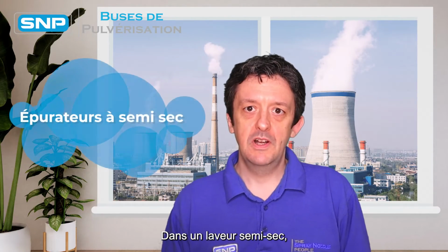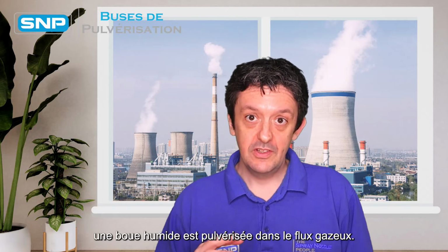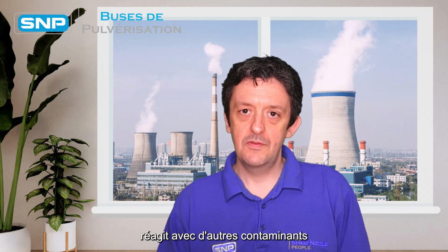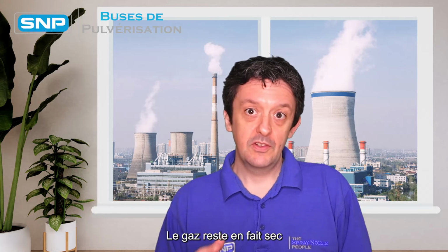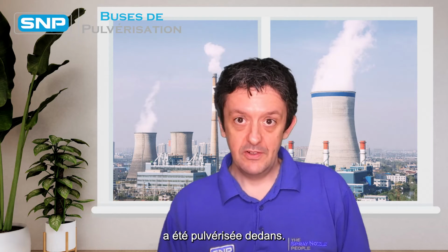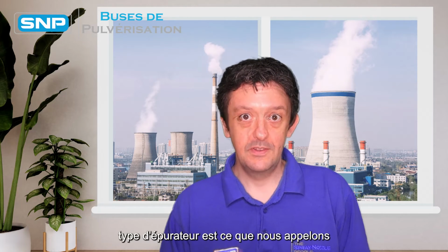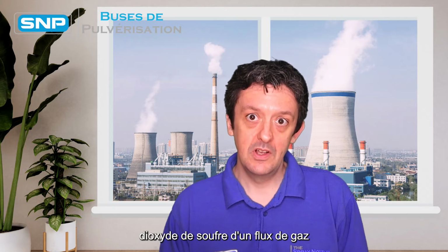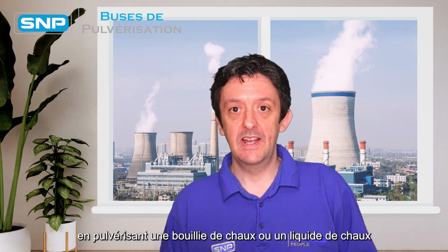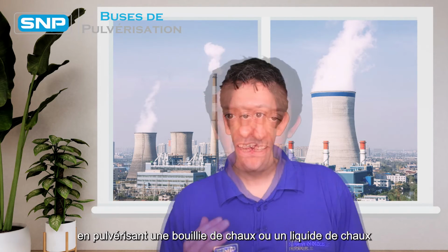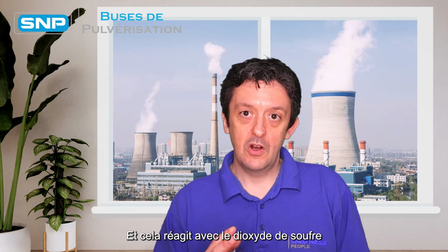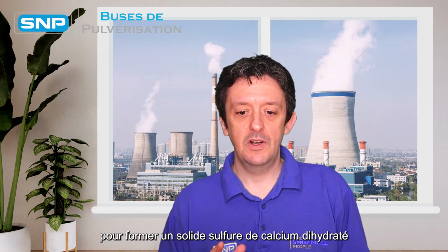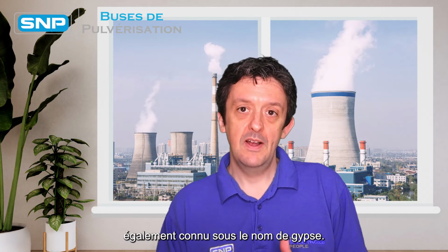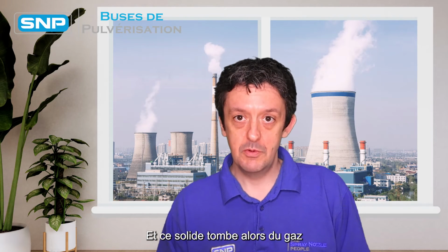In a semi-dry scrubber, a wet slurry is sprayed into the gas flow, and this then reacts with the contaminants in the gas to form a solid. The gas actually remains dry despite the fact that a wet slurry is sprayed into it. Now, the most common type of scrubber is used for what we call flue gas desulfurization. So this is removing sulfur dioxide gas from a gas flow by spraying a lime slurry, lime liquid, into the gas, and this reacts with the sulfur dioxide to form a solid calcium sulfate dihydrate, also known as gypsum, and this solid then falls out of the gas and is removed as a contaminant.